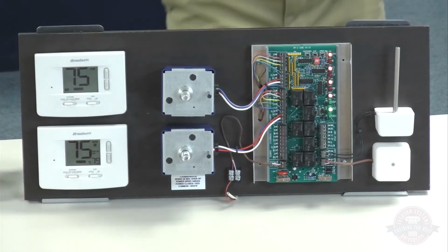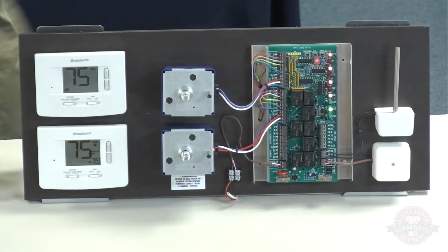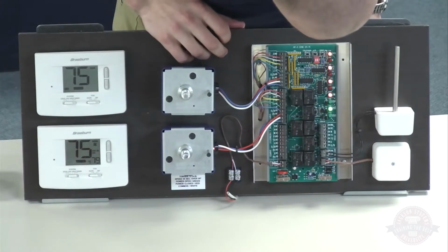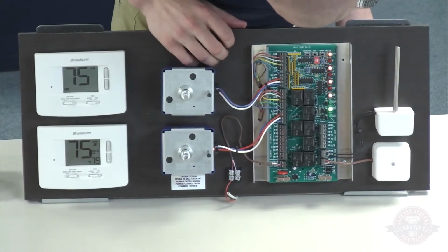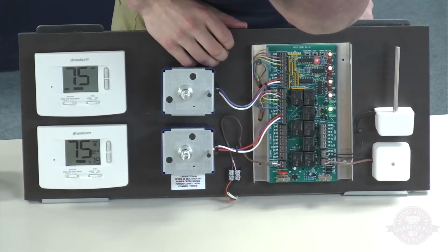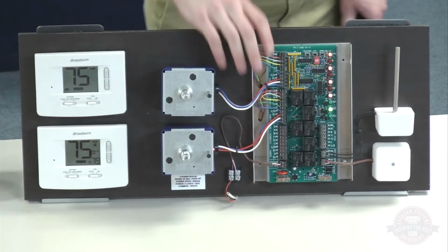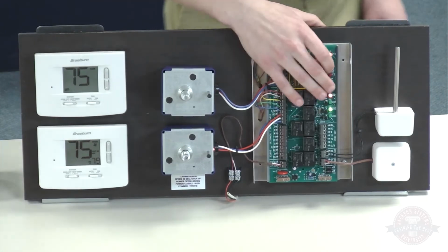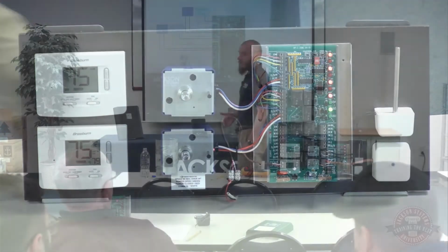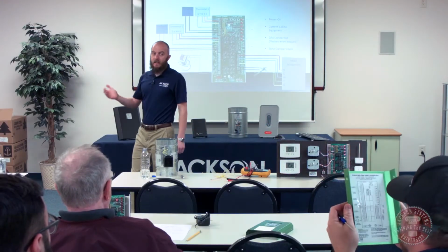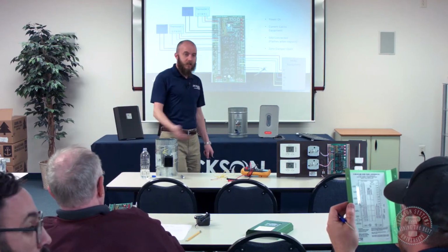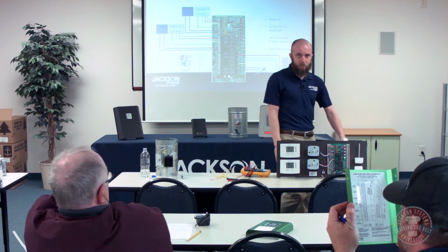There we go. So when you get a call, the appropriate lights should light up on the board. In this case, I have a heat pump board set up for a B-type reversing valve. So I have a Y1... that's not right. That thermostat's probably not set up right. So I have a Y1 and I have a G call on my board. Those LEDs should match the relay output of the board, the signal going out to your HVAC system.